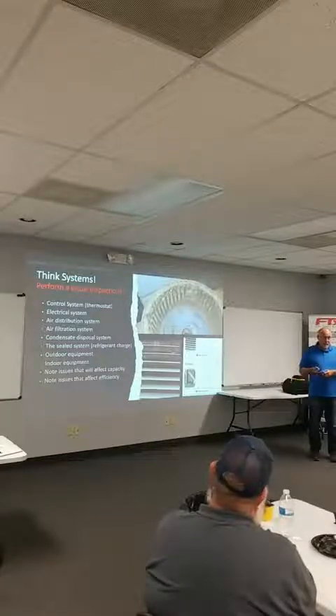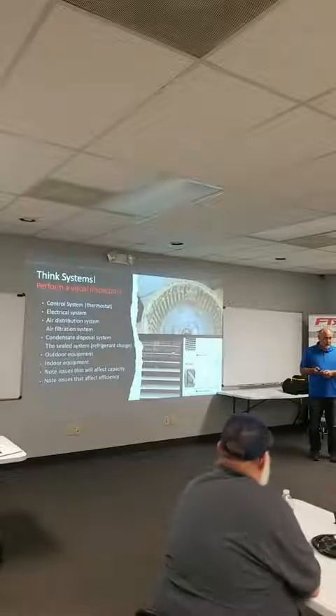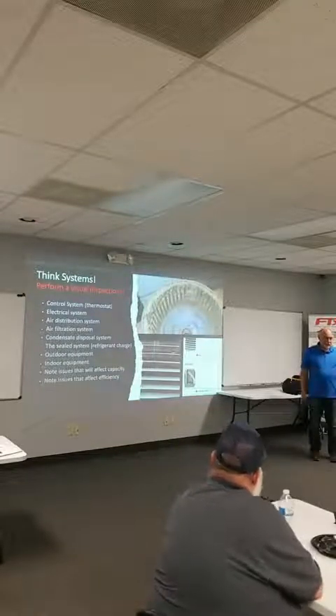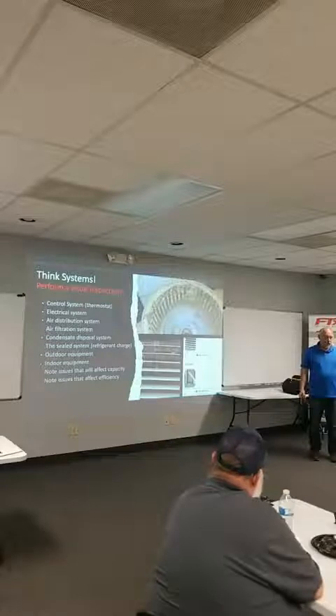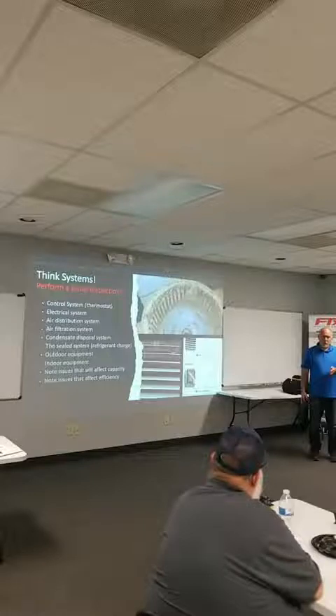One of the big mistakes we make in our industry is we quit putting in sight glasses years ago because everybody thinks they're for checking for bubbles in the refrigerant. No, that's actually a moisture indicator. That eye in there was to tell us if the system was dry, right, or purple, or whatever it was. Back in the day, there was a company, I can't remember who it was, that made a fortune off adding dryers. One of the mechanicals in town here, all they did was put dryers and sight glasses on things because all these systems were wet. Everything was wet. And they knew it, and they'd get these systems straightened out, and they would run like tops for a long time.